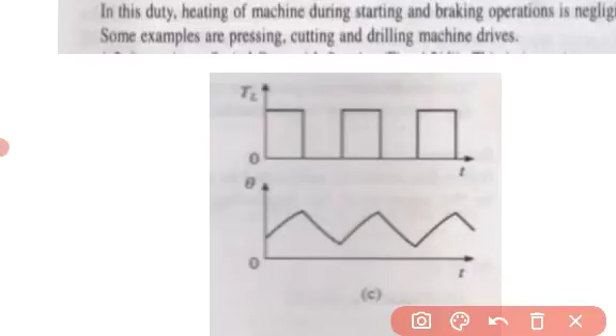I will take the pen. The steady state temperature will not be reached, nor does it fall to zero. Before that, loading is applied again. Here you can see this is the load. When the load is removed, the temperature decreases. Both things are here: one is that it is not allowed to reach the steady state temperature rise, and the second is that it is not allowed to cool down to zero. Hence the operation is called intermittent periodic duty.